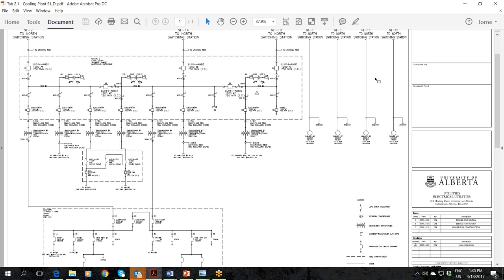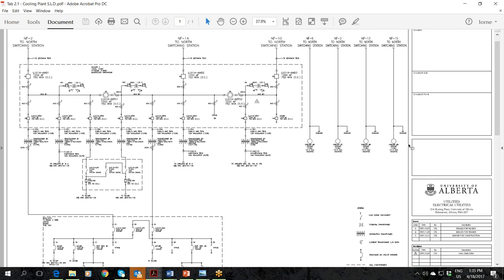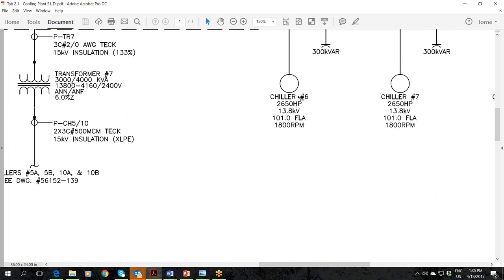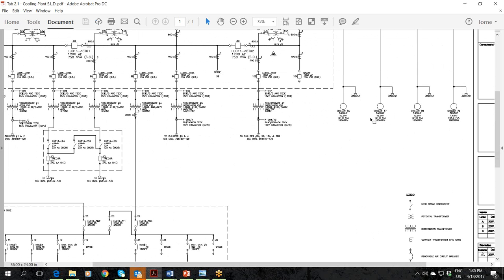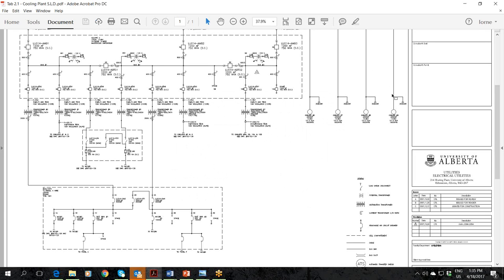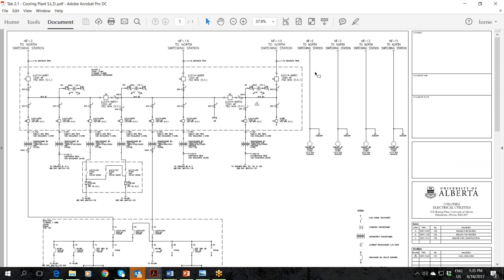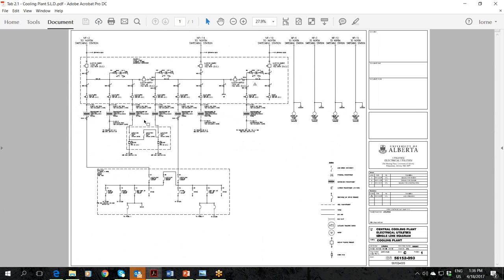One thing that is kind of interesting, we've got our largest chillers at this original cooling plant, so 2650 horsepower. I've certainly heard of larger motors, but those are the largest ones that we have, but they're directly operated off of breakers in the north switching station. So the 13.8 kV breakers are used to operate these 4 chillers. That's how the system was originally configured.